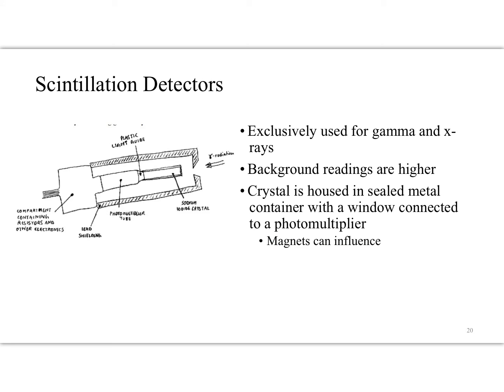Considering different types of detection equipment — one of the first the textbook mentions is the scintillating detector. We use these quite a bit as well counters in nuclear medicine. They're used exclusively for gamma and x-rays. They're very sensitive to background radiation, so you have to calibrate them to the background, and they can be influenced by things like magnets. Basically you have a crystal that glows in the presence of radiation, fed through a photomultiplier and then read out. It has a bunch of lead shielding around it because it's so sensitive.